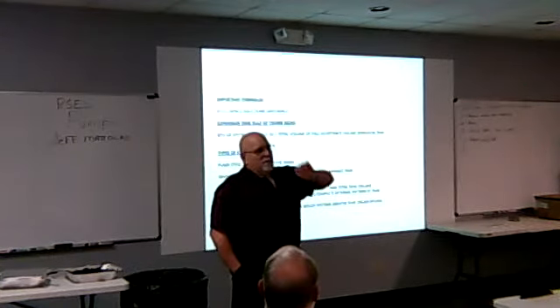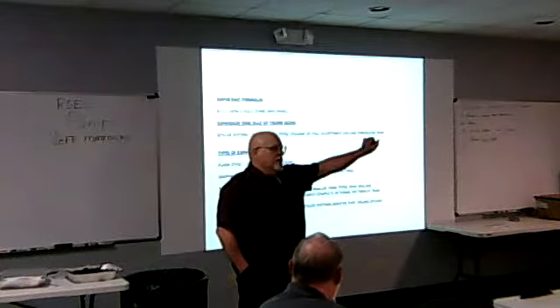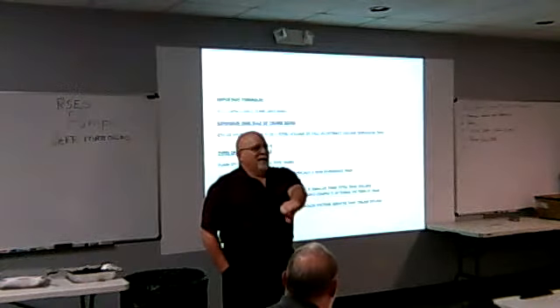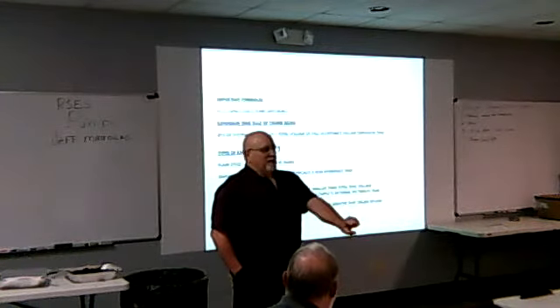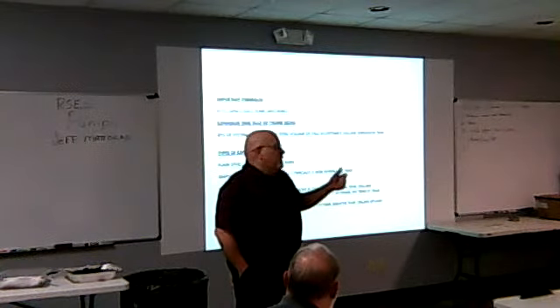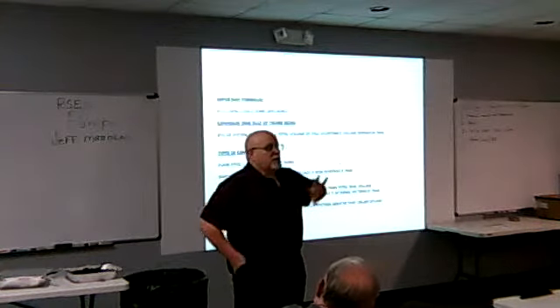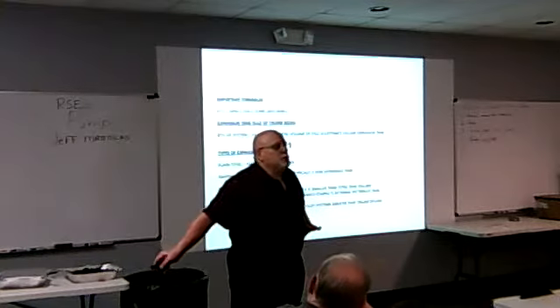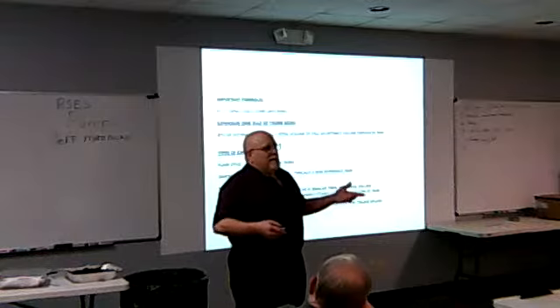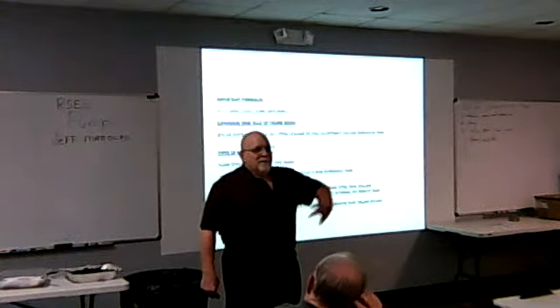We size expansion tanks based on fill temperature, max temperature, system volume, starting pressure, and relief valve setting. And we always size up to 5 pounds below relief valve setting. That system is going to go up in pressure regardless. If you want a 20-pound fill pressure and want it to stay at 20 where you expand all that water, your expansion tank's the size of this room. It's going to be huge. It's going to cost you $100,000. I got a 150-pound system. My fan coils are rated for 200. My fin tube's rated for 400. My valves are rated for 400.